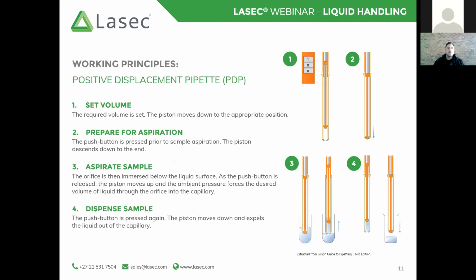Okay, so how the positive displacement working principles work, very much similar to the air displacement pipette, now with the piston housed in the tip itself. So this piston is now going to come in contact with your solution, and that's why positive displacement pipettes generally use what we call a capillary piston. This is a disposable tip, much like the air displacement pipettes, but it now has two parts, which consist of that piston as well as the tip.